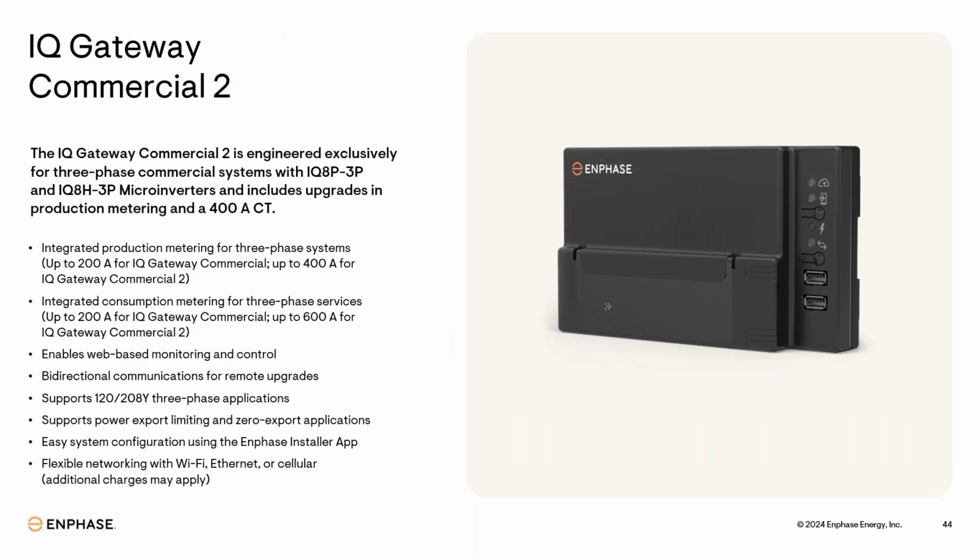Commercial gateway, I'd mentioned the commercial gateway. This is our new commercial gateway 2. The commercial gateway is the brains of the system. So all of the microinverters connect to the commercial gateway. They're run into branch circuits, as we had mentioned before, going into a 3-phase combiner. And then this gateway connects to the 3-phase combiner and receives all of the information from the microinverters by PLC, power line carrier communication. So there's no extra cables. You don't have to hook up any sort of Ethernet cable between microinverters. That's all done through the power lines, and that comes into the gateway.